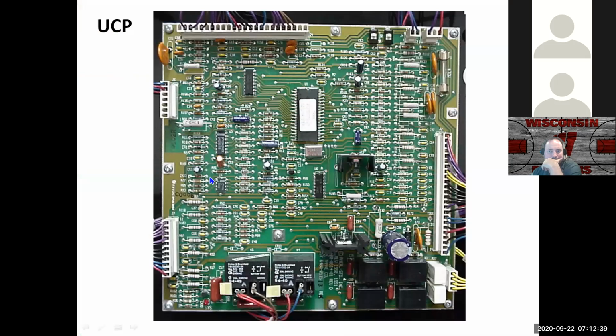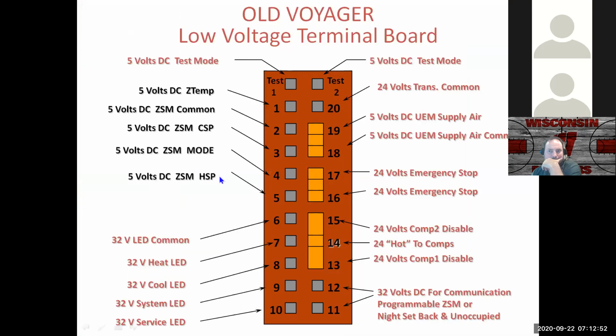All right, this is the old board, the UCP board, and it basically did the same thing that the new boards do, but the technology's changed a little bit. With the old UCP board, we had to use this 1 through 20 terminal strip. If you look at them on the older units, the 1 through 5 is still your 5 volt DC. That didn't change. And then the 6 through 14, again, is our 32 volt system. That really didn't change either.